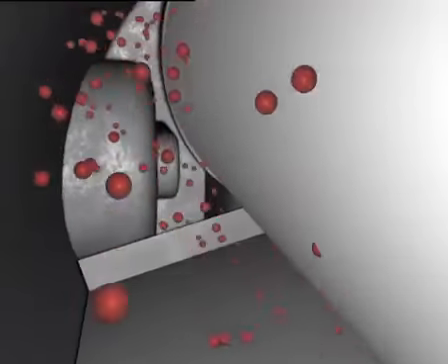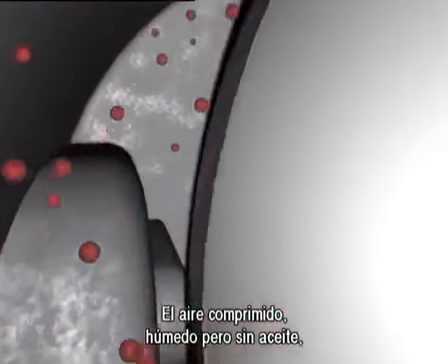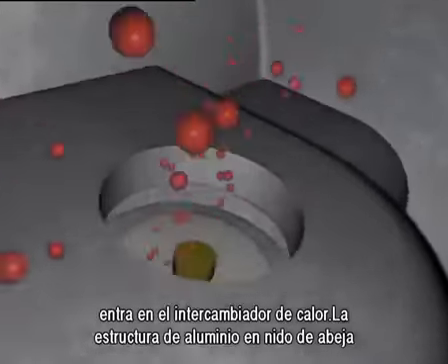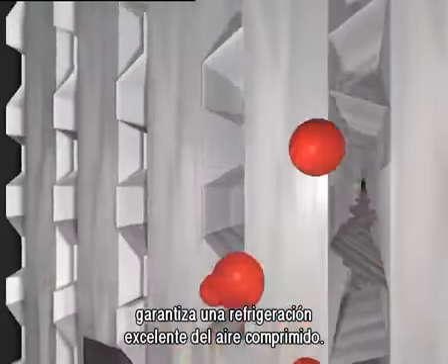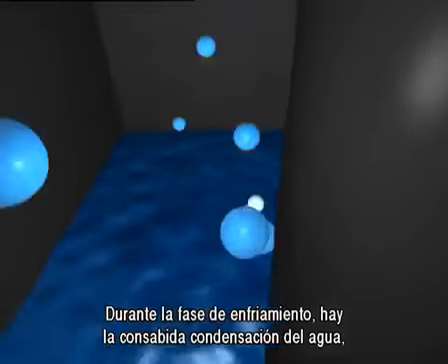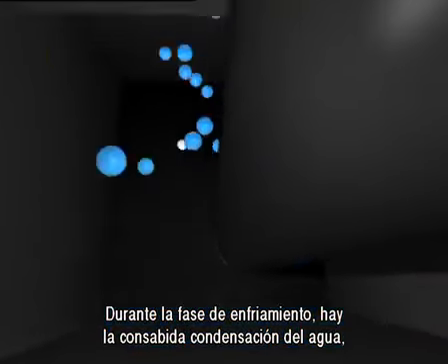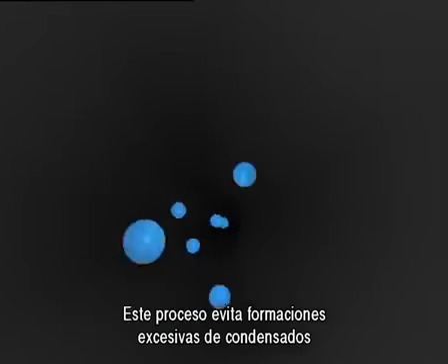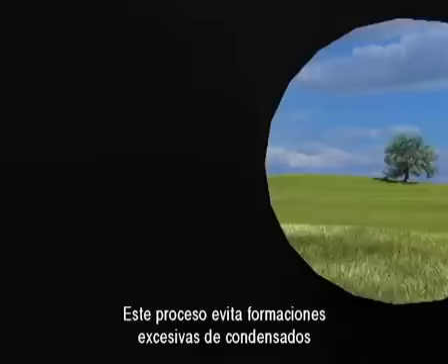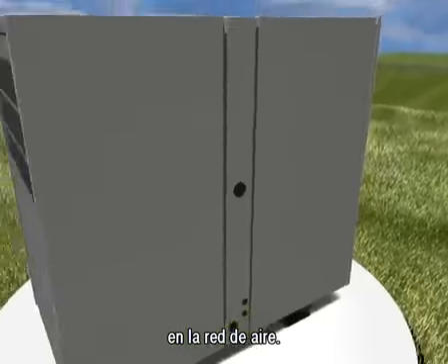After the oil separation, the damp compressed air reaches the heat exchanger. The honeycomb aluminium structure guarantees an optimum cooling of the compressed air. During the cooling stage, the water condensates. This will later be separated in order to prevent the formation of too much condensate in the air distribution.